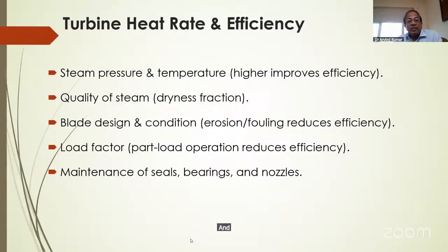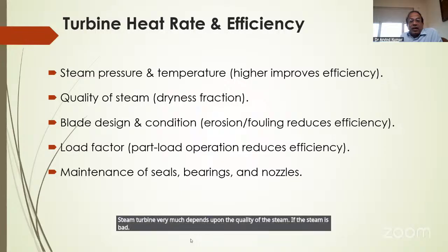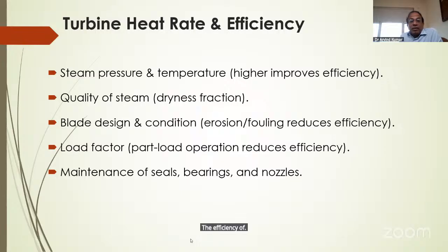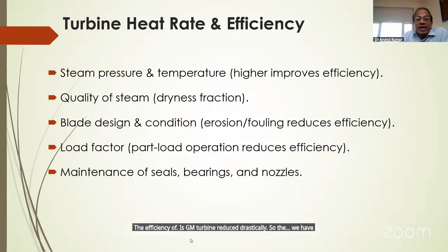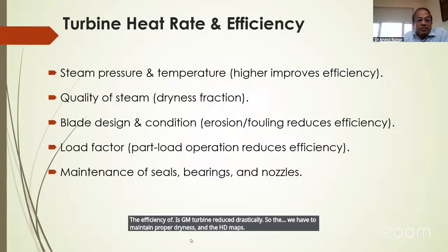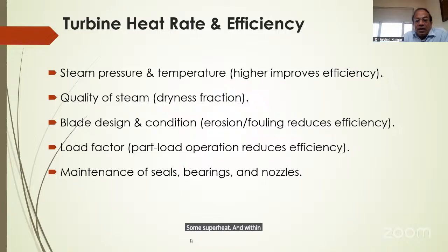And quality of steam: a subcritical steam turbine depends very much upon the quality of steam. If steam is bad, the efficiency of the steam turbine reduces drastically. So we have to maintain proper dryness, and the steam should have some superheat. Within the turbine, steam remains in expansion mode, dry. So we need sufficient superheat throughout the expansion process until the steam comes out.